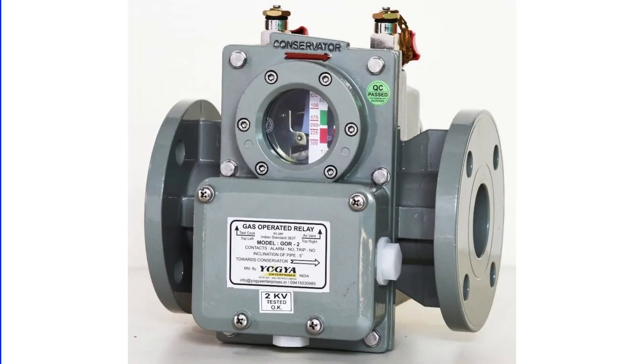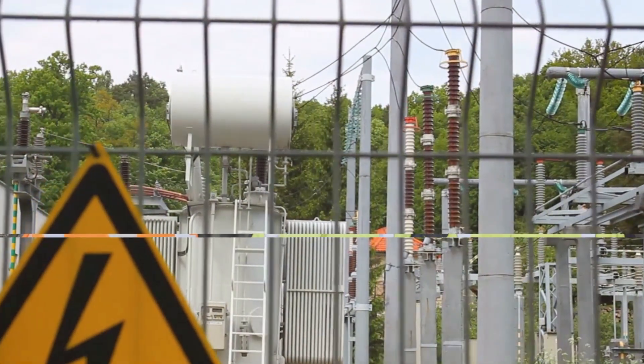Lastly, we have the Buchholz relay, a gas-actuated device which detects faults by monitoring gas accumulation in the transformer. This relay serves as an alarm or trip element, depending on the volume of gas or the speed of oil loss. Mechanical protections are essential to prevent potential physical damage to the transformer.